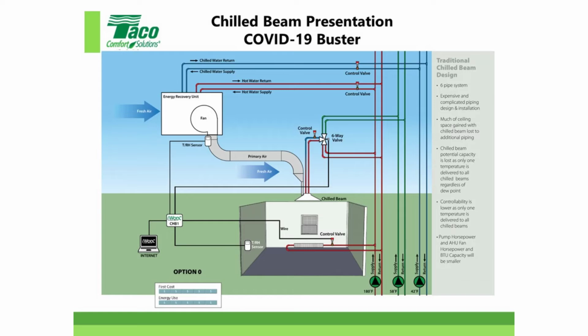Then you have the warm cold water. That just doesn't make sense. I say it so many times I get confused. But this is warm cold water, so that's 58 degrees, 55, 56, whatever, above the dew point. Right? And you can adjust that as it goes, and we have variable speed pumping.